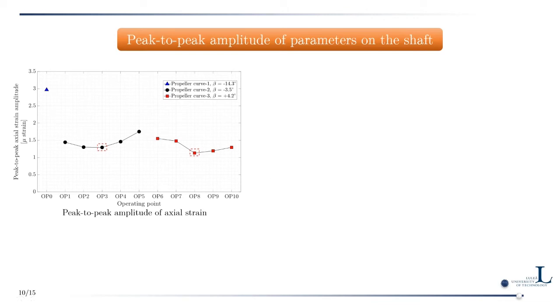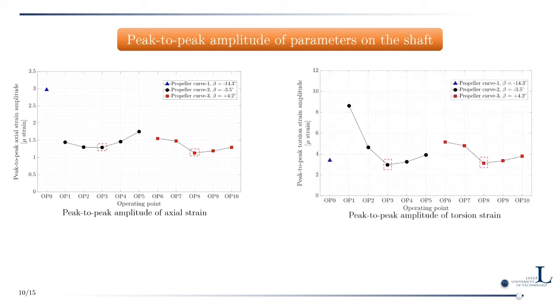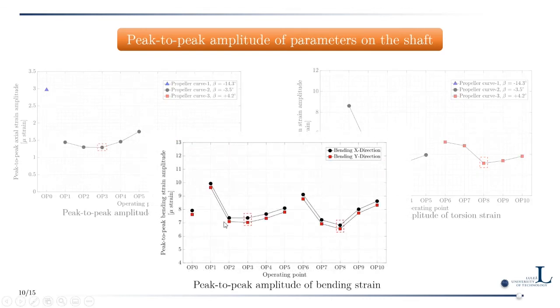Peak-to-peak values of axial strain (left) and torsion strain (right) on the shaft also show local minimums at OP3 and OP8 for both cases. This confirms that operating points with minimum peak-to-peak strain amplitude on the shaft also correspond to minimum peak-to-peak pressure and strain amplitude on the blade — both aligning with the best efficiency point of the propeller curves. A similar result is observed for bending strain.